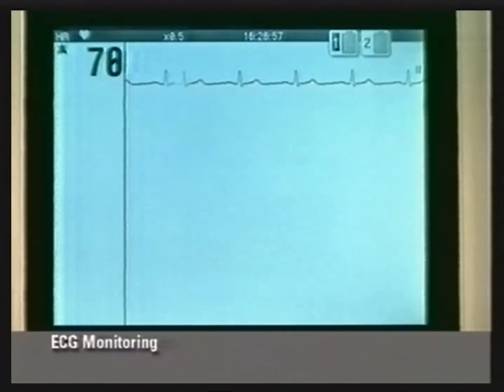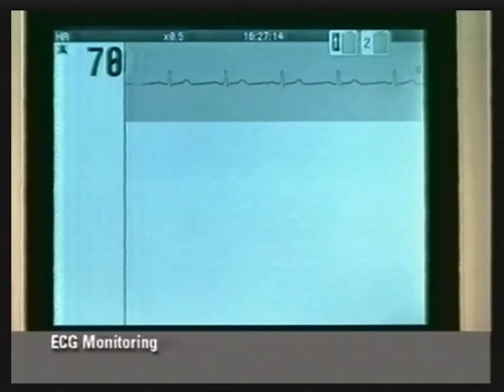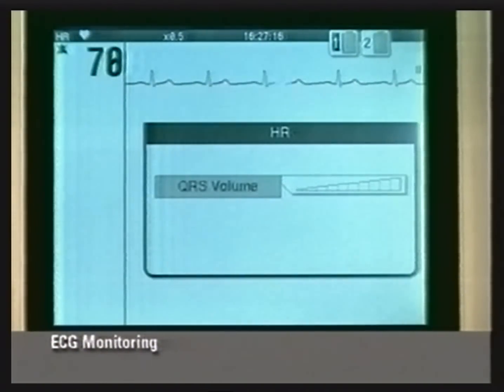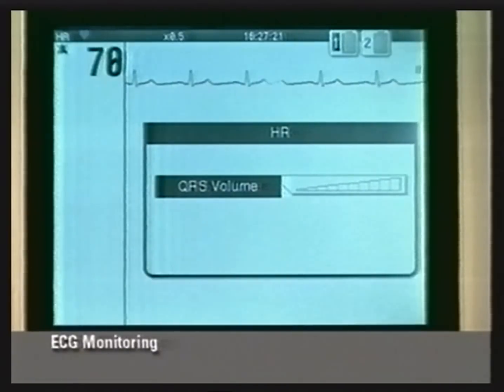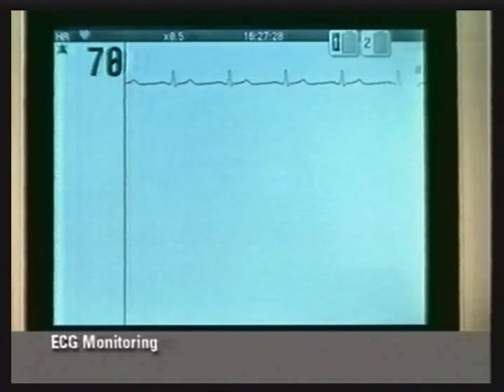Check that the ECG size is adequate for heart rate counting. If the ECG size is too small or too big, heart rate counting may be inaccurate. The heart symbol should flash, and the systole tone should sound once with each QRS. To adjust the systole tone volume, highlight the heart rate area, press the selector to display the heart rate menu, press the selector to black highlight QRS volume, then rotate the selector to increase or decrease the systole tone volume.